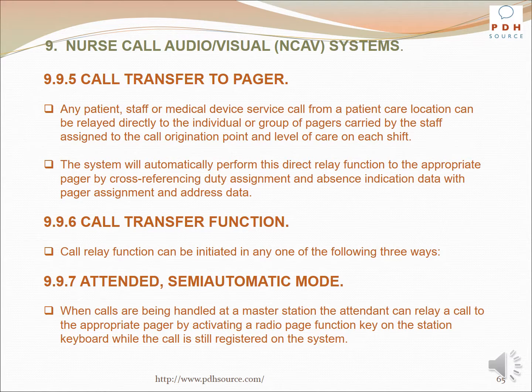Any patient, staff, or medical device service call from a patient care location can be relayed directly to the individual or group of pagers carried by the staff assigned to the call origination point and level of care on each shift. The system will automatically perform this direct relay function to the appropriate pager by cross-referencing duty assignment and absence indication data with pager assignment and address data.